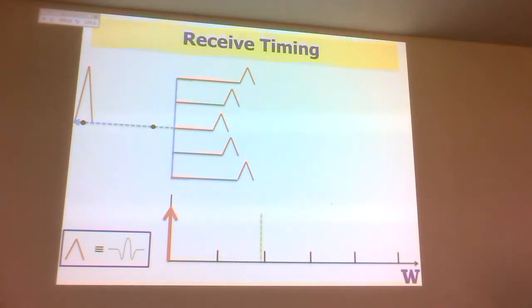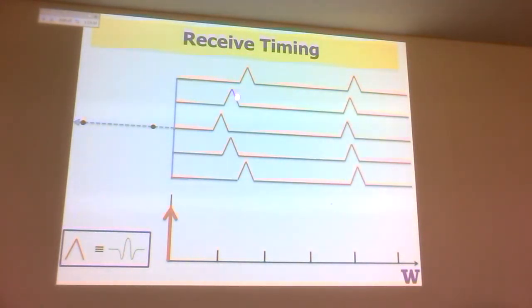But the wave keeps propagating. So at some time later, I'll hit the second target. Right? When do those waves show up? 2 times that, so over here somewhere, right? Do they have the same curvature as this one? No. But I can rephase that. And what I didn't show is, when you're really close, these elements may have some distortions, so I'll just use some center elements. As I go deeper, I'll use all elements, but keep this constant NA as I go. So you have a constant spatial resolution, you have a constant in range by controlling the pulse, and you have a constant in the other 2 dimensions by controlling the aperture. Until eventually you've got the full aperture open, and in the far field of all images, you'll start to see blurring, because you've run out of aperture.